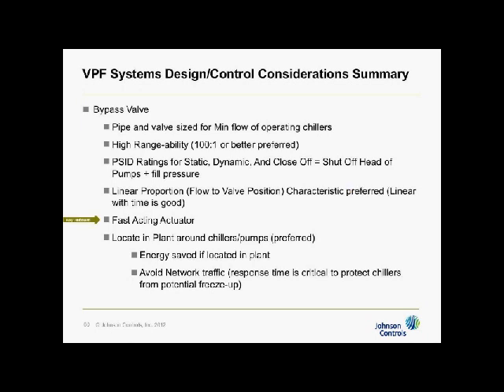It needs to be a fast-acting actuator. The fast action is needed to protect the chillers from freezing. Just like the control for the variable speed drives on the pumps, the control for this also needs to be fast-acting. And what that means is that you need to locate it so that you can direct wire it.